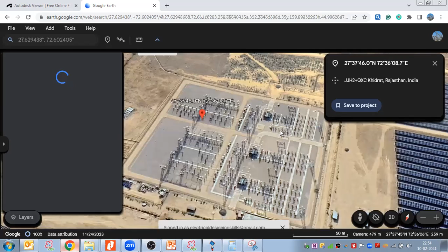So whatever the site environmental condition is, that will also affect your system design. Make sure that whatever equipment you are purchasing and whatever calculations you are doing, you are following that particular site data or site environmental data during equipment procurement and calculations. Therefore, for the design of substations and equipment selection, since equipment rating depends on site conditions, equipment selection is important.